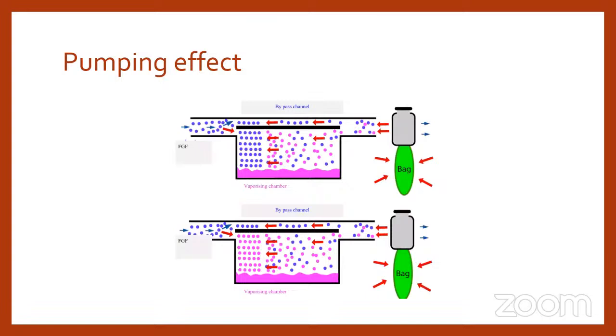Usually what happens is, whenever the fresh gas is administered, it is divided into two chambers: the bypass pathway and the vaporizer chamber. In the vaporizer chamber, it mixes with the vapors that are present in the chamber, and it will come out of this outlet and mix with the bypassed fresh gas, and it will be delivered to the bellows or bag that we use to ventilate the patient.